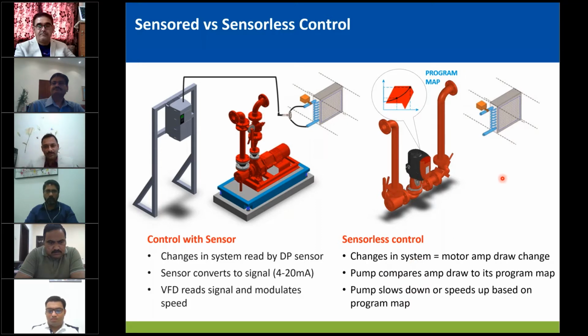Now coming to sensorless control, it changes whenever there is a change in the system behavior or demand. The first thing that senses the change in pressure or flow requirement in the building is the pump, because it's a closed circuit, and as we know from the pump affinity laws, when pressure and flow change, amperage changes. So once you have embedded program maps inside the controller of the pump, it becomes smart, and by reading amperage from the inbuilt control sensors, it can go into the map and provide you the actual operating point and sense the demand of the building.